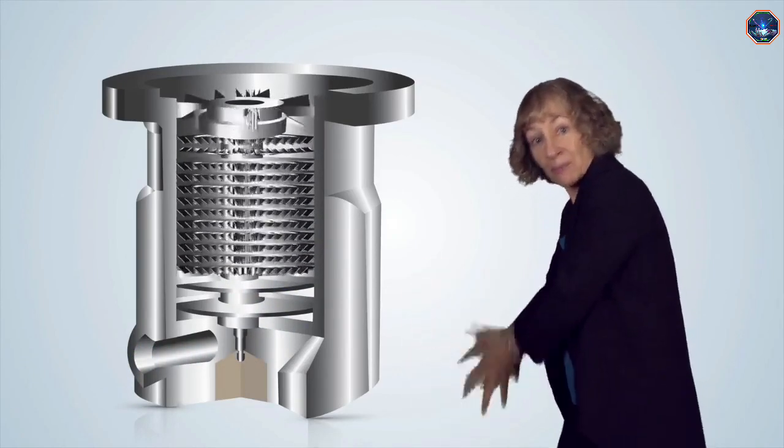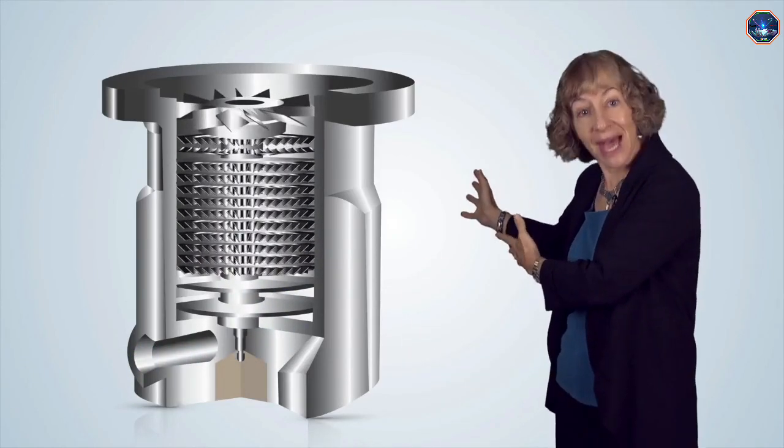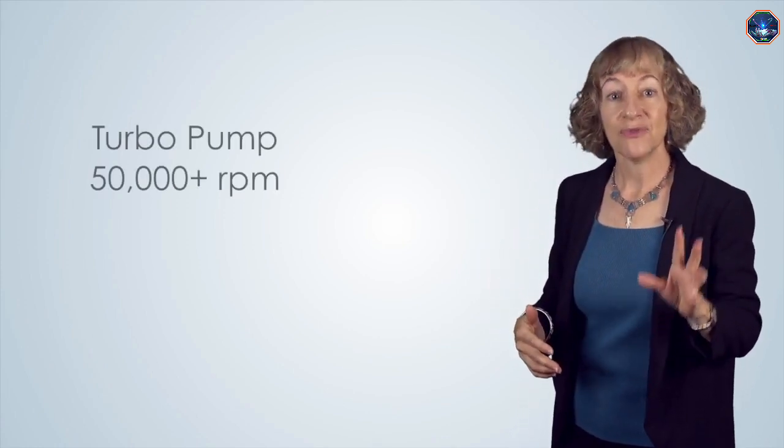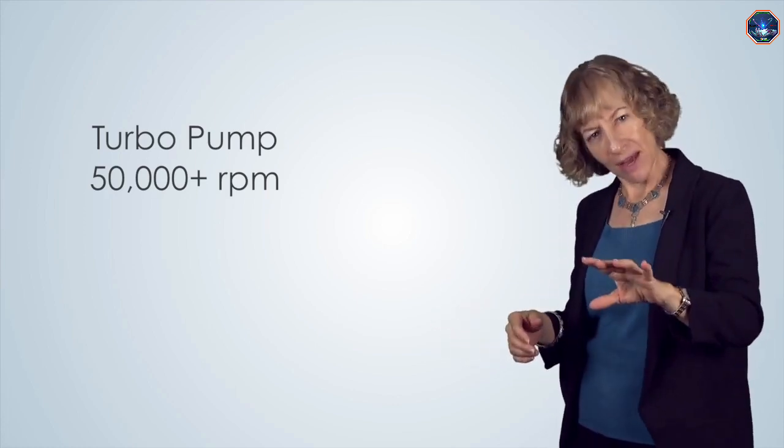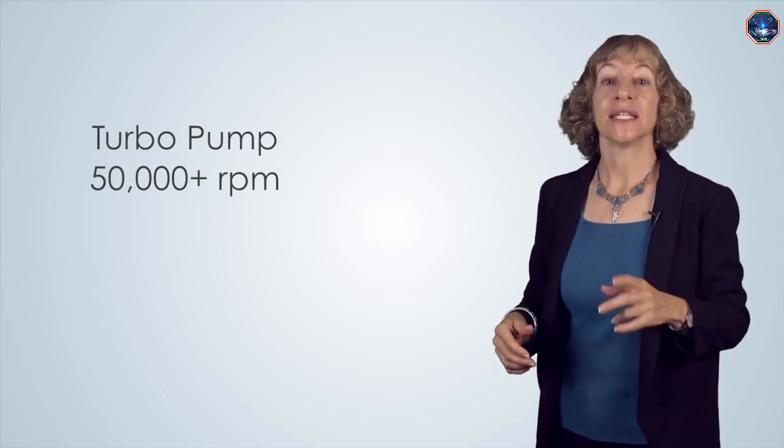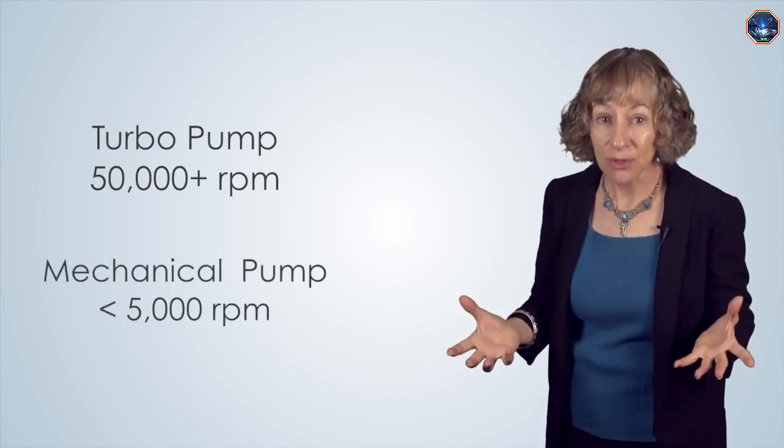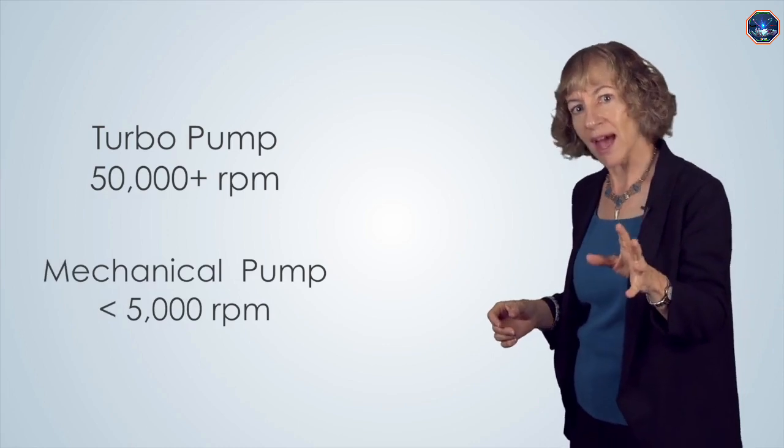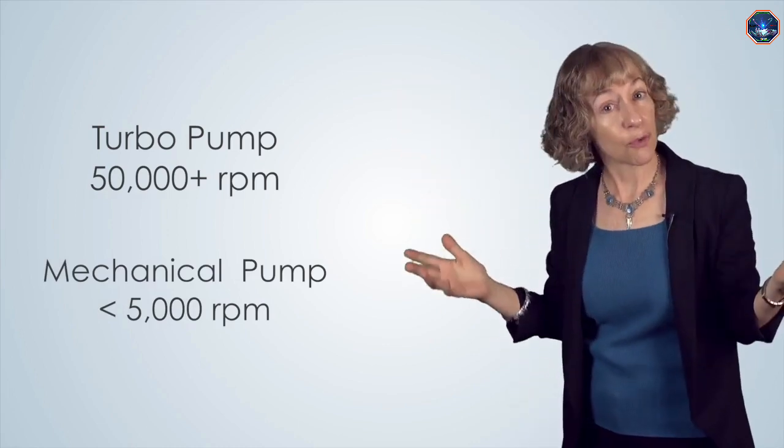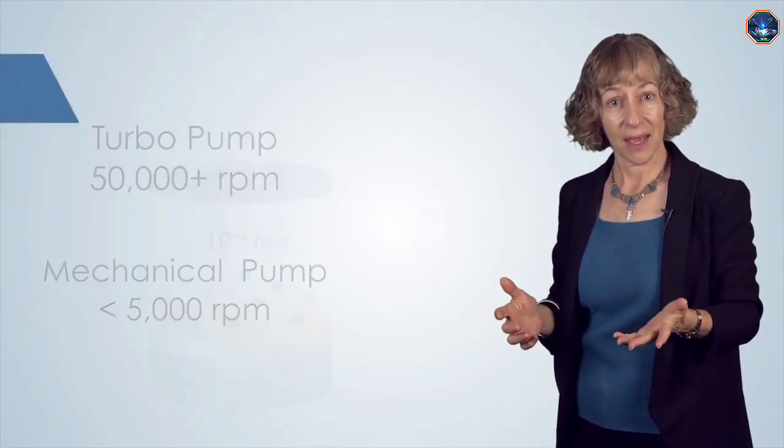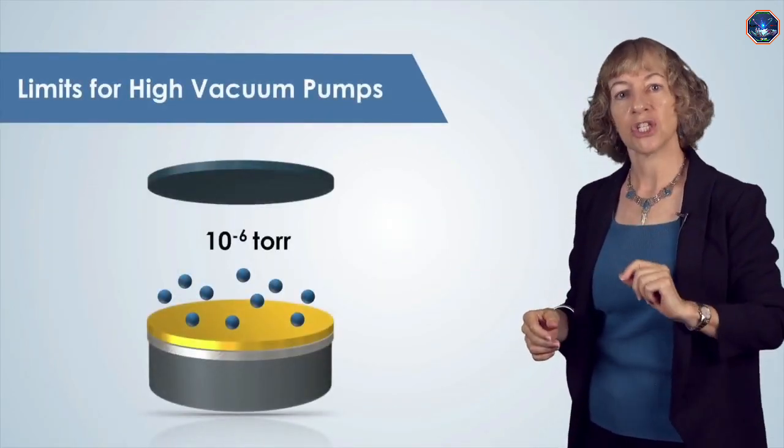The air molecules that the turbo pump collects make their way out of the outlet of the turbo pump, which then are pumped by the mechanical pump that is backing the turbo pump. The pumping ability of a turbo pump is related to the speed of the turbines, which typically spin at 50,000 revolutions per minute or more. Compare that to a typical mechanical pump which rotates at less than 5,000 revolutions per minute. Now this is still pretty fast—a helicopter rotor typically spins at only 400 to 500 rpm.